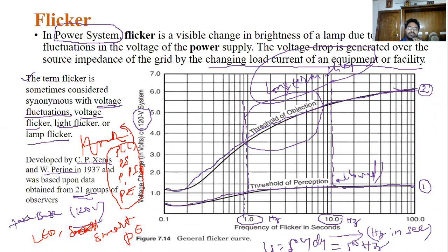For example, in an automatic packing industry, when a flicker happens, the PLC and its power electronic devices see sudden voltage changes, so instead of packing at one position, it packs the second one and one is left out. So there is a huge economic loss because of these flickers on the industry side. Remember.